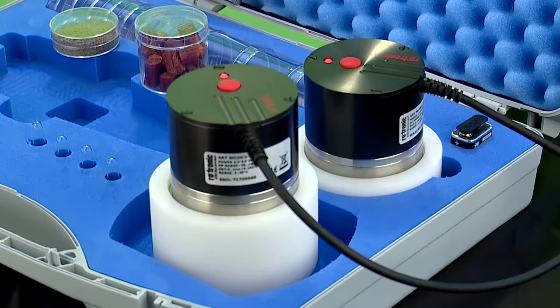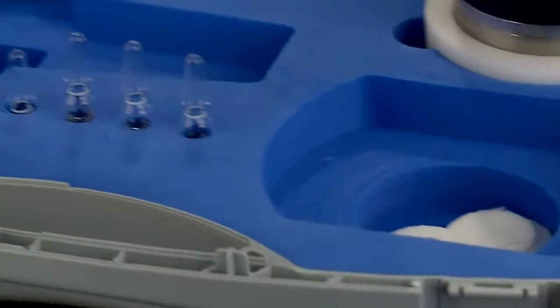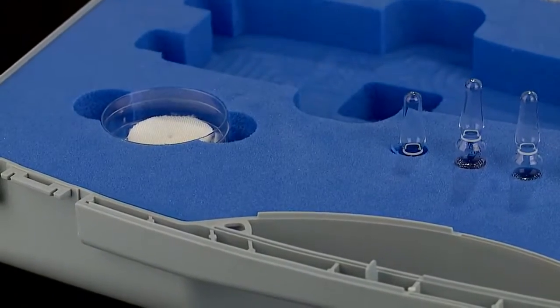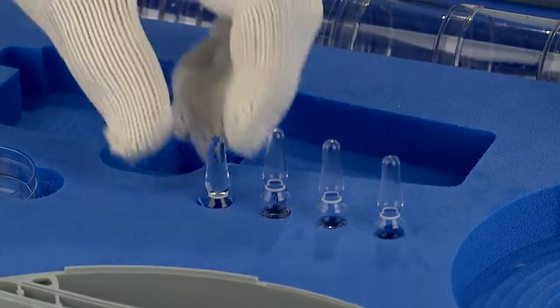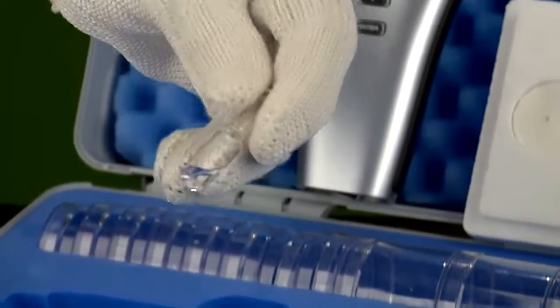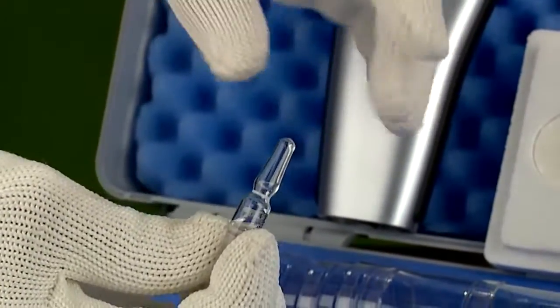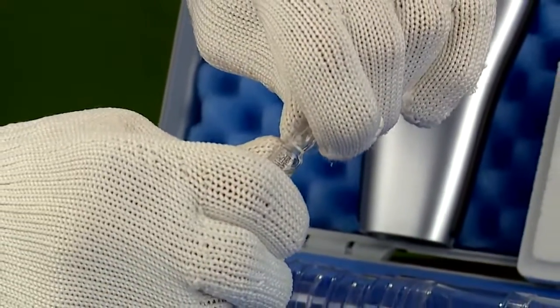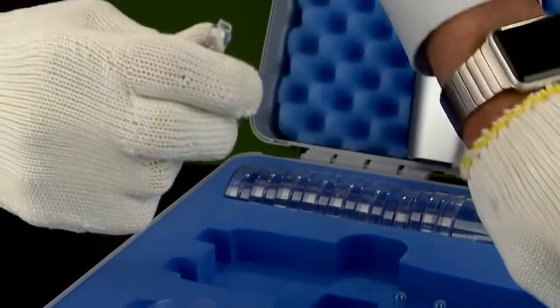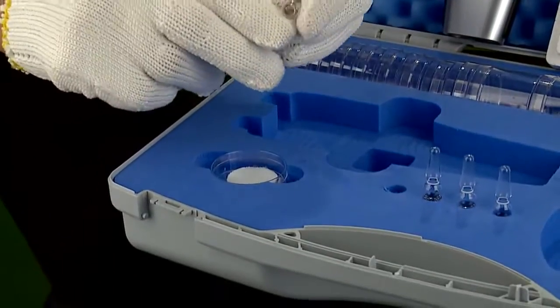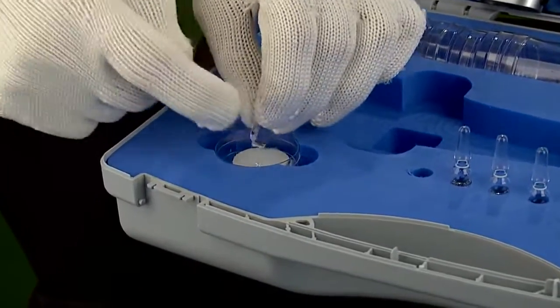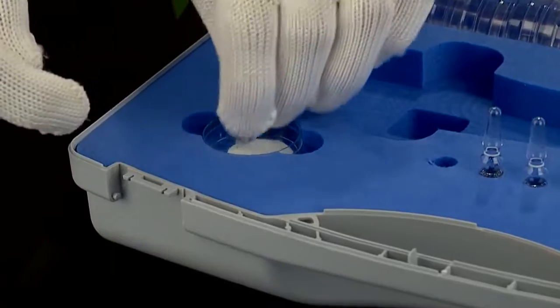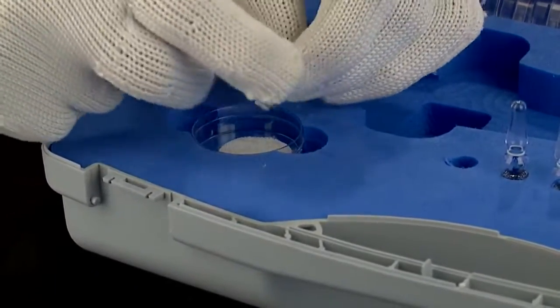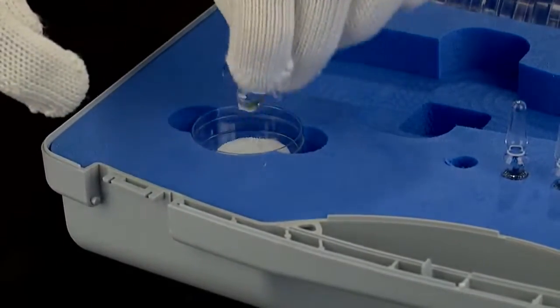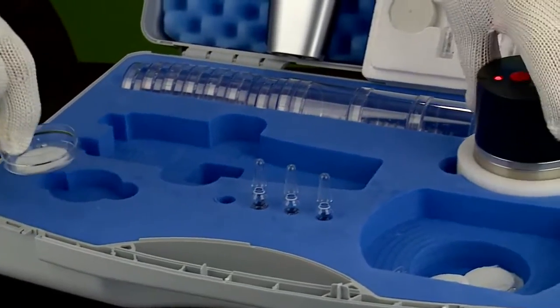To start the calibration, using a small sample cup, place one of the cloth discs into the sample cup. Tap the top half of the vial to ensure all the liquid is in the bottom half of the vial, and then break open the calibration vial. Here it is important to note that the vial is glass. Use safety gloves and safety glasses and break the vial open facing away from you. Empty all the liquid onto the cloth pad and dispose of the used vial properly. Each calibration solution should soak with the probe on the solution for a minimum of 45 minutes.